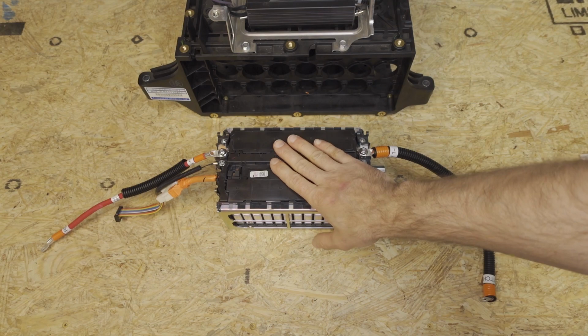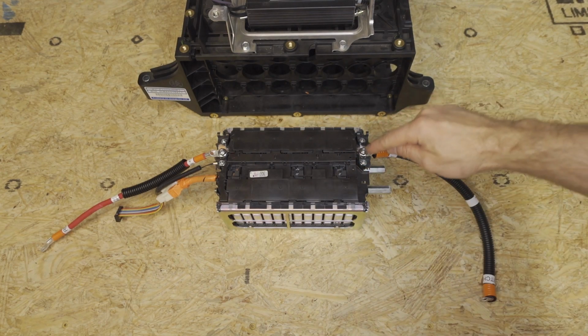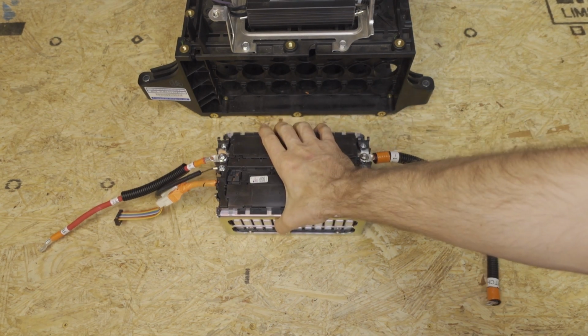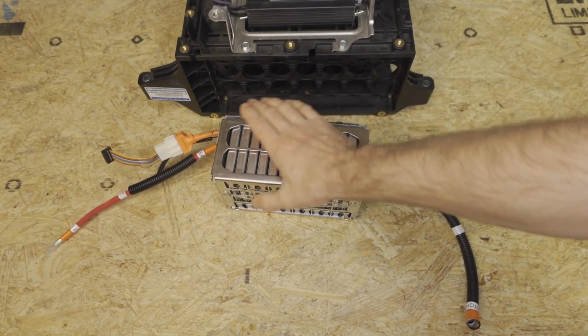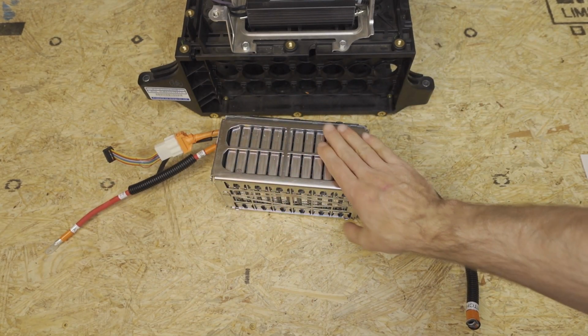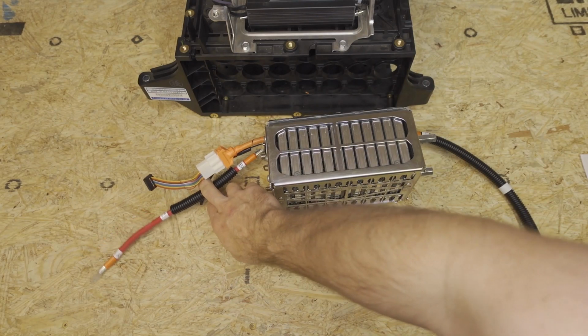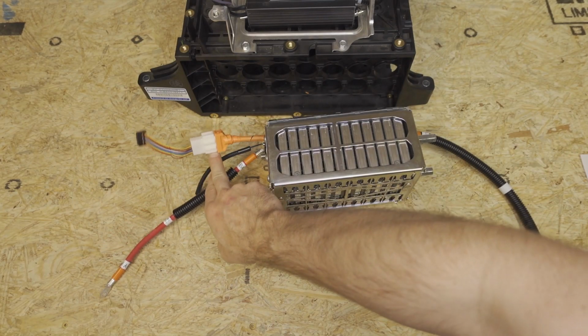With both cables installed on module 1, we're going to route the high current cables down. That will always be the case on all modules, no matter how you install them. The high current cables will always be below the battery management cable.